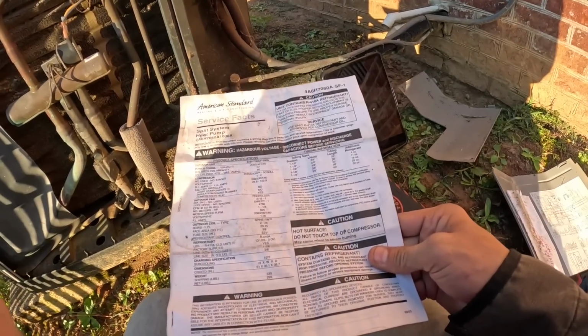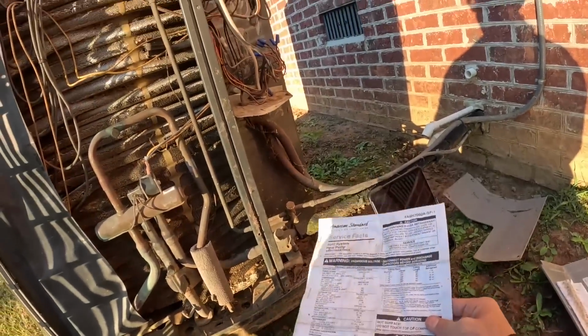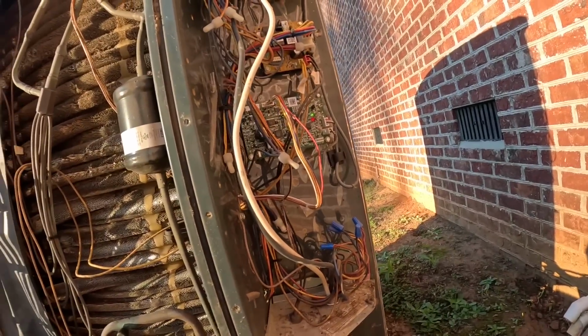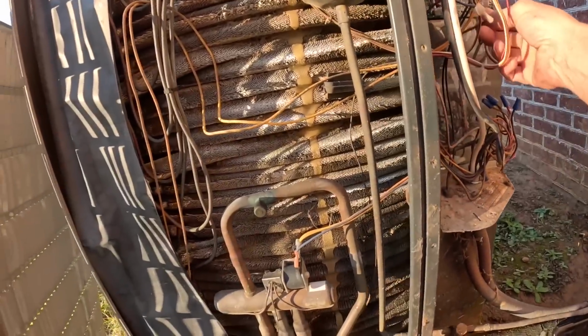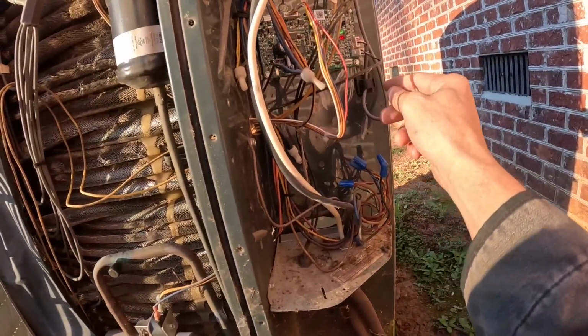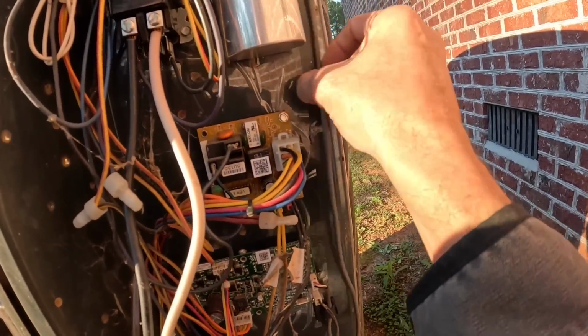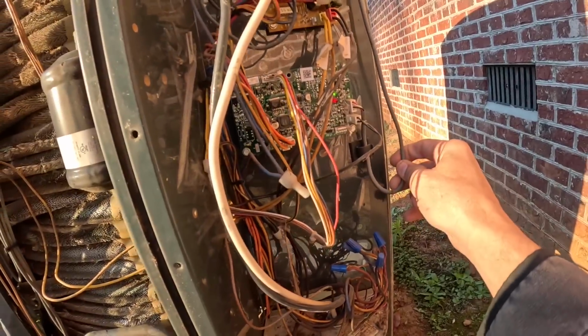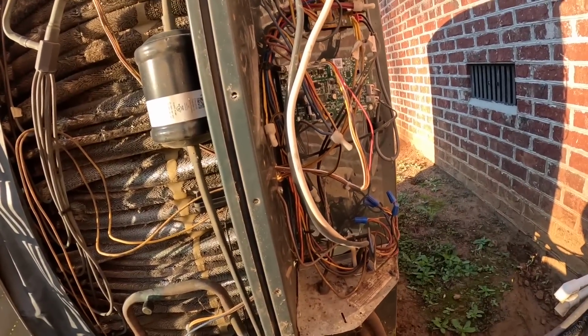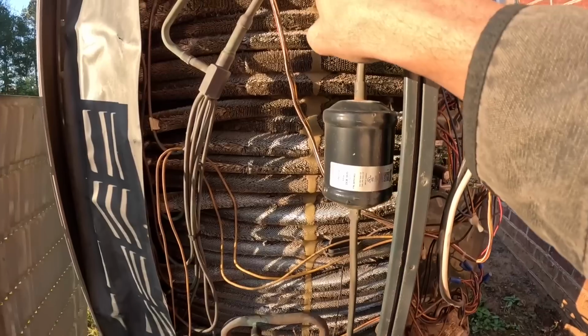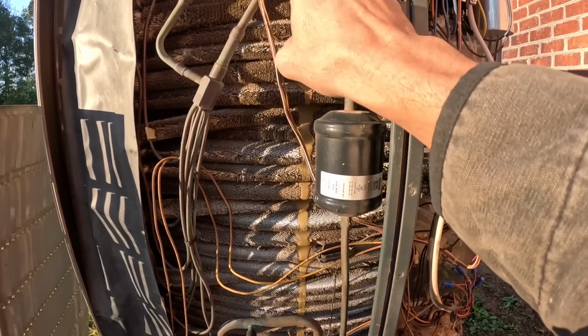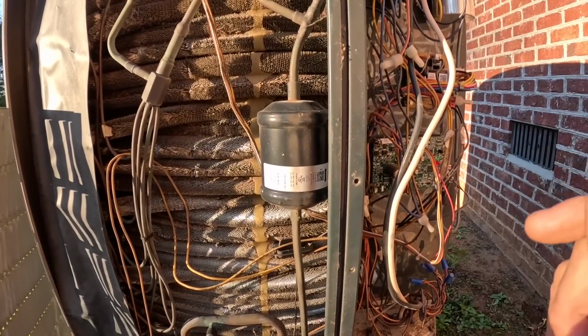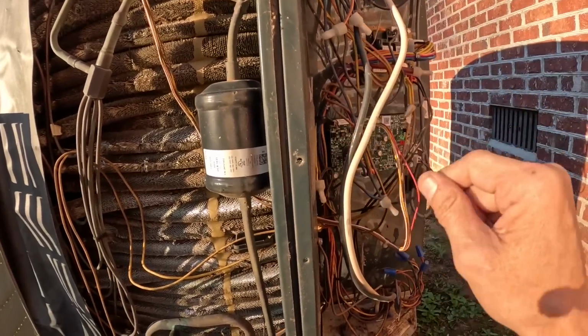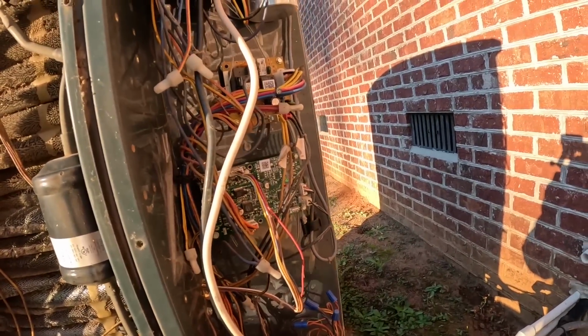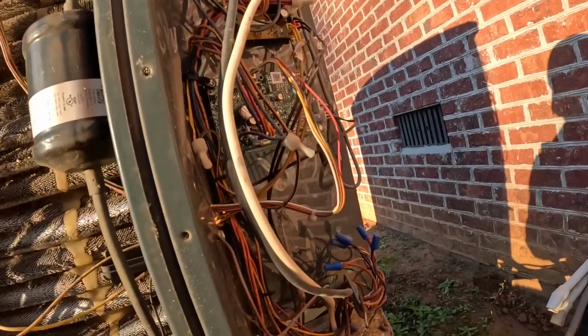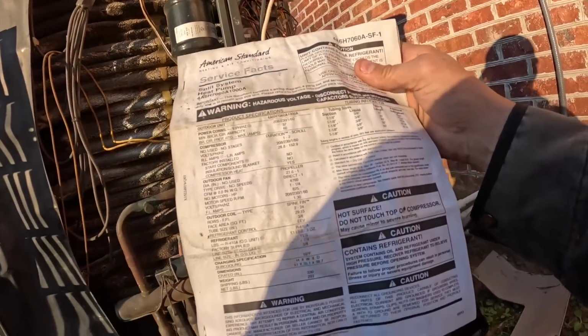Here we go. Well, before I do too much, I am back and I did a little bit of research on this, and I think we have a temperature sensor here that could be out of whack, and this, if I'm not mistaken, may go to a pressure transducer. So we need to check those before I go replacing this coil. I think I'm going to replace the coil anyway, because I did find one of them that was open. Replace the coil, but before I replace the board, I'm going to try to figure out with these service facts what my ohm readings are supposed to be.